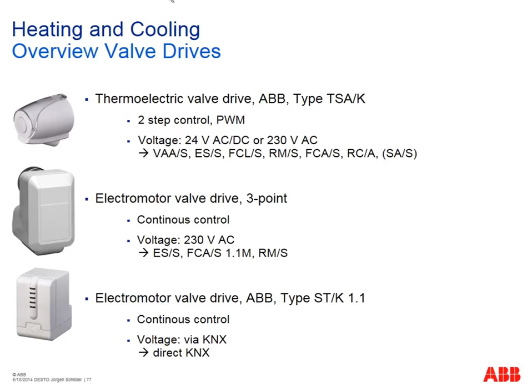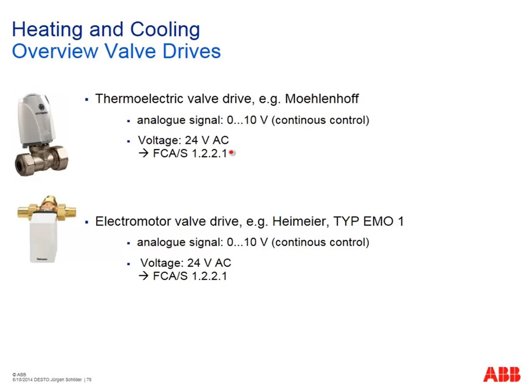Additionally, on the market you sometimes find valve drives controlled via 0 to 10 volt. So you need an analog signal in this case. Two examples of 0 to 10 volt valve drives. One is controlled via a thermoelectrical principle, one controlled via motor. We have the fan coil actuator FCA/S 1.2.2.1 to operate this, and in some cases you need such a component. In former times we had only the analog actuator, still possible to use, but it does not have the dedicated software to do so. So this is the right device for this kind of valve drive you might have in a project.